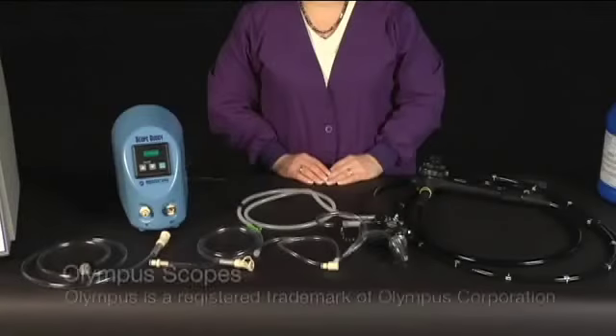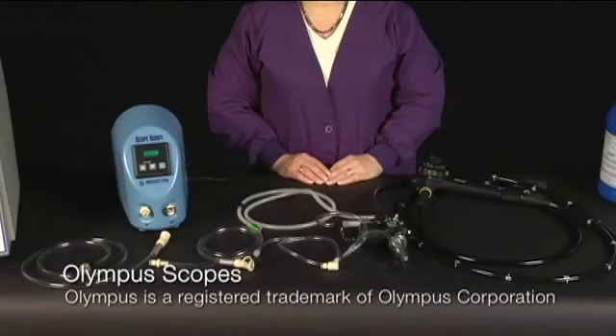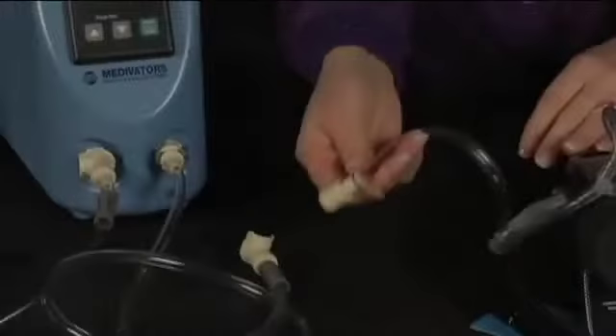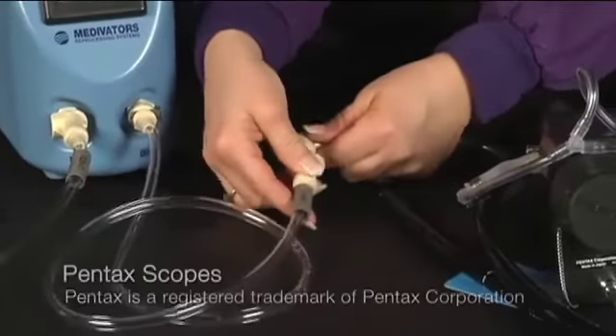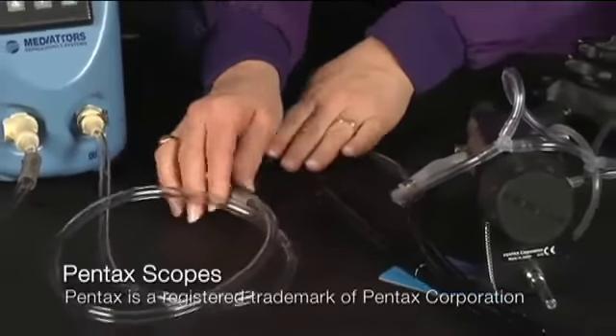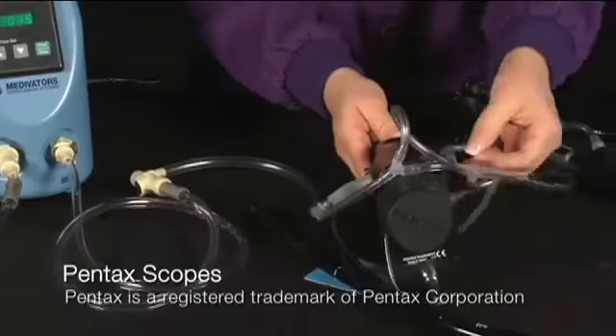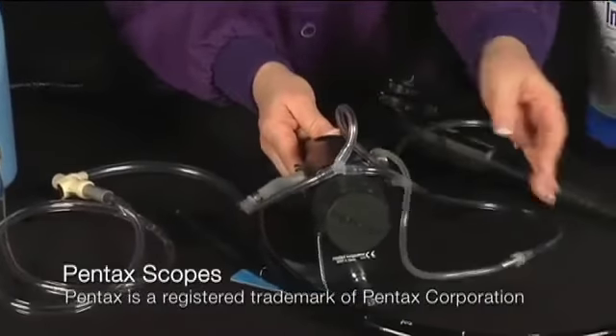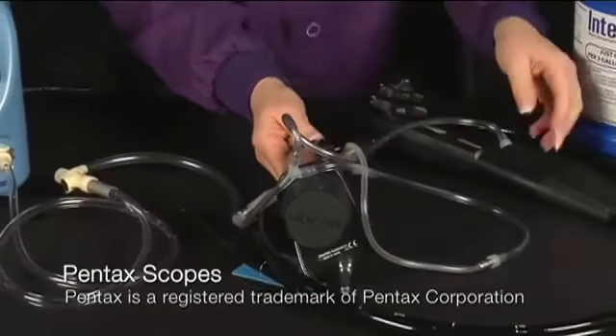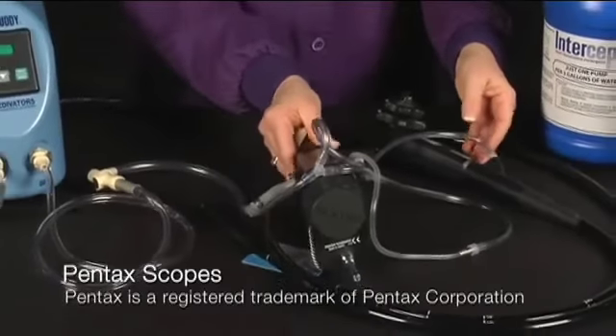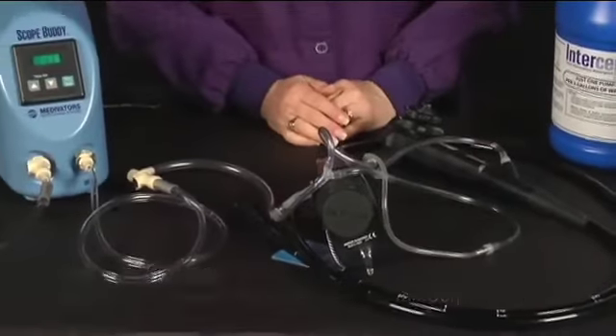For Olympus scopes, the auxiliary water channel and elevator wire channel of an Olympus endoscope do not require the use of the elevator wire channel hookup and can be flushed simultaneously with the other channels using the DSD hookup. For Pentax scopes, the forward water jet or elevator wire channel of a Pentax endoscope do not require the use of the elevator wire channel hookup and can be flushed simultaneously with the other channels using the appropriate DSD hookup.